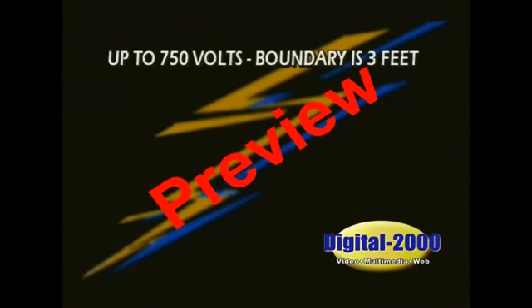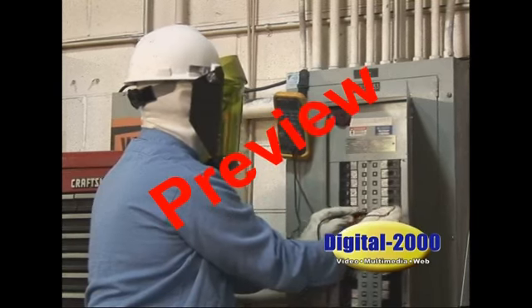Generally, up to 750 volts, the boundary is 3 feet. 750 volts to 2,000 volts, the boundary is 4 feet. 2,000 to 15,000 volts requires a 16-foot boundary. 15,000 to 36,000 volts of electricity require a 19-foot boundary. Any voltage over 36,000 must be independently calculated.